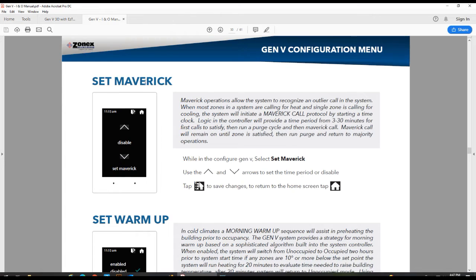Set Maverick mode. This allows you to see outlying calls. So if you enable this, and for example, you have 3 cool calls and then a heat call comes in, the Maverick mode will see that call, and based on a time given between 3 and 30 minutes, the timer will start. Once that time lapses, we'll then drop the call, go into a purge cycle. After 5 minutes, we'll bring in the heat call, and we will run that heat call till it satisfies.